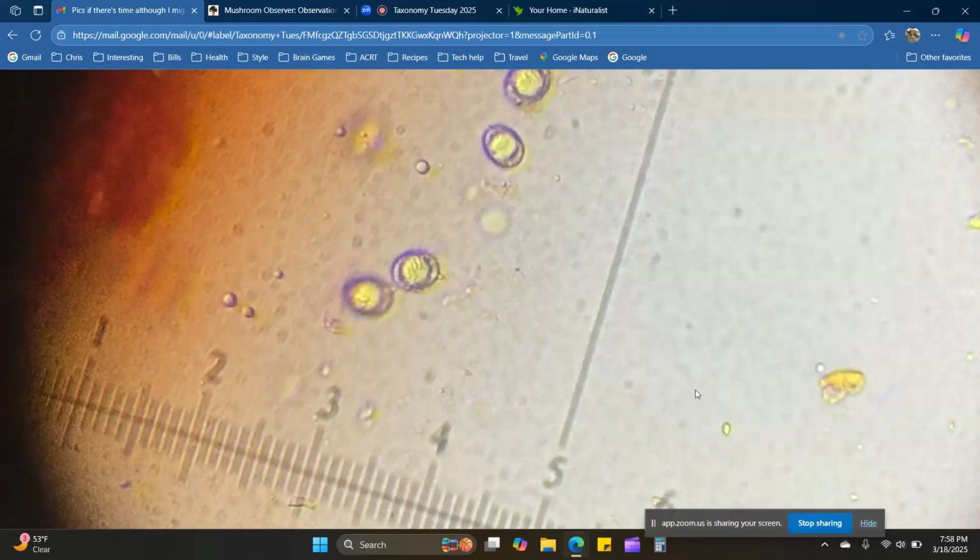Thank you. And then of course at each magnification there is going to be a little lever on the side that you have to also move. It's going to actually have positions written, times 10, times 40, and times 100 and so forth. So every time you switch your magnification, that carousel with the optics, to the appropriate lens, you should also move that lever on the condenser accordingly. Igor, that's the iris, right? Yeah, the lever is going to adjust the iris, the pupil.